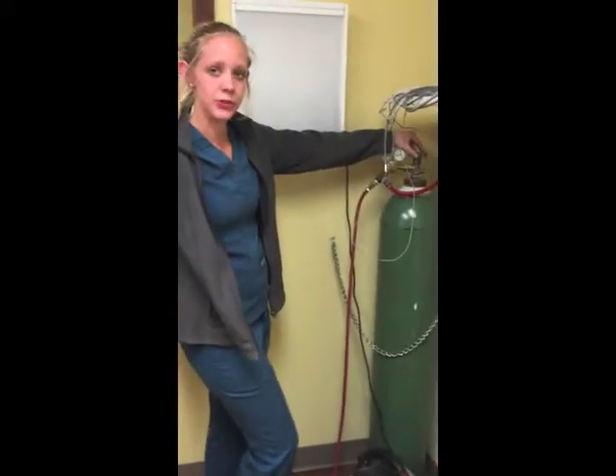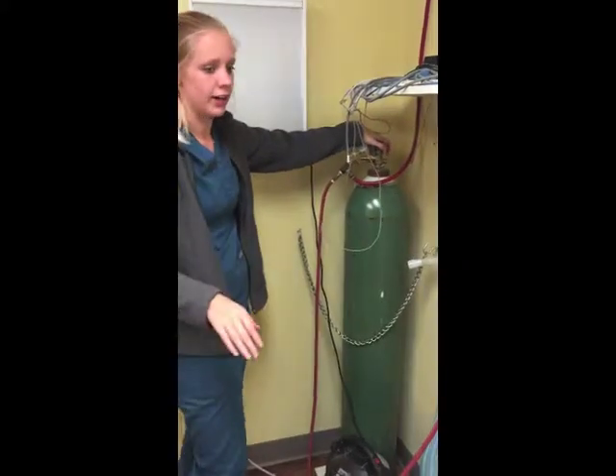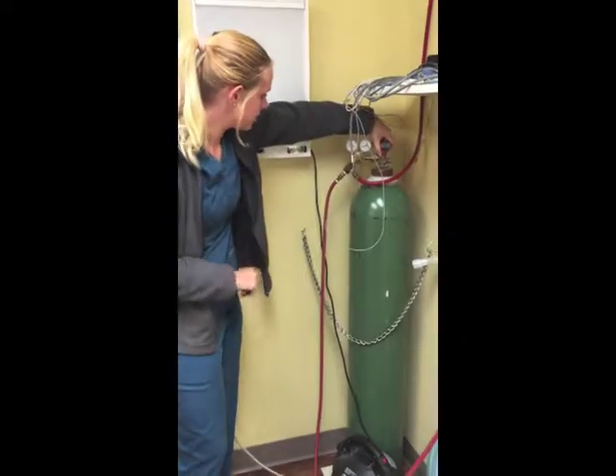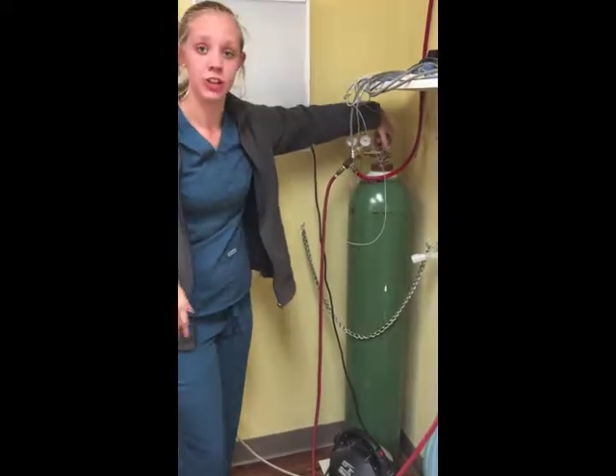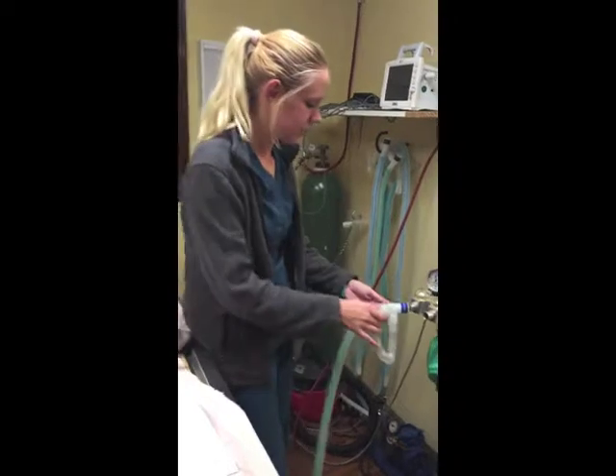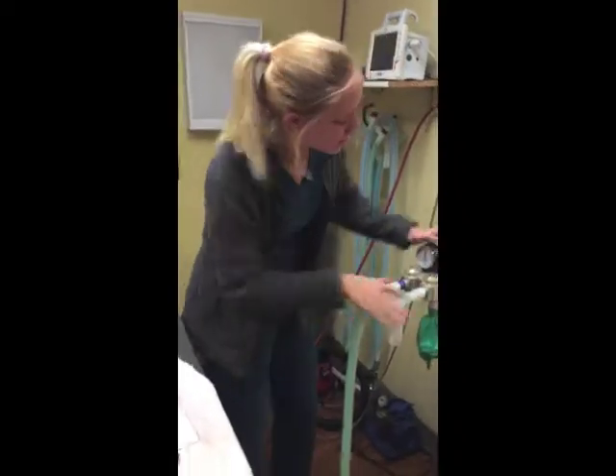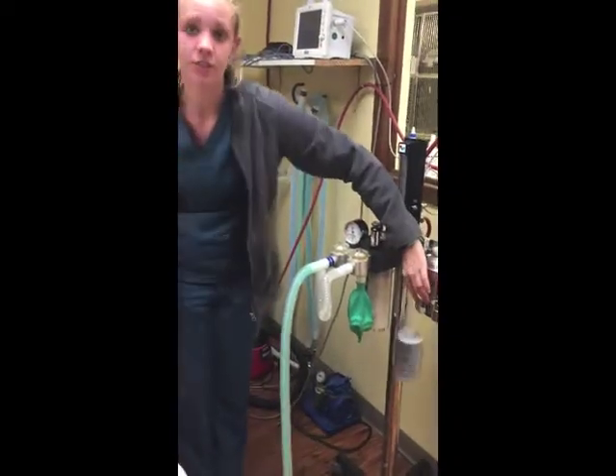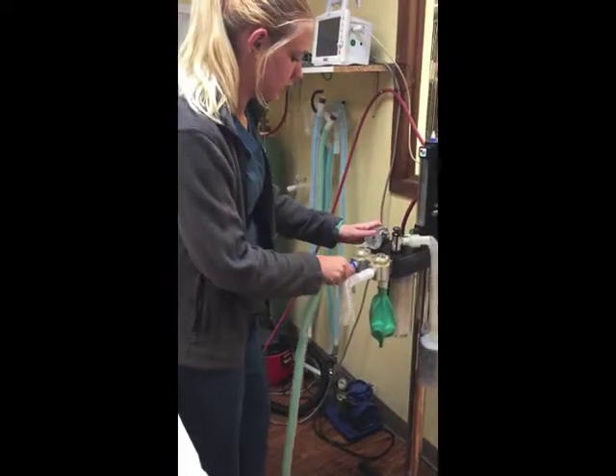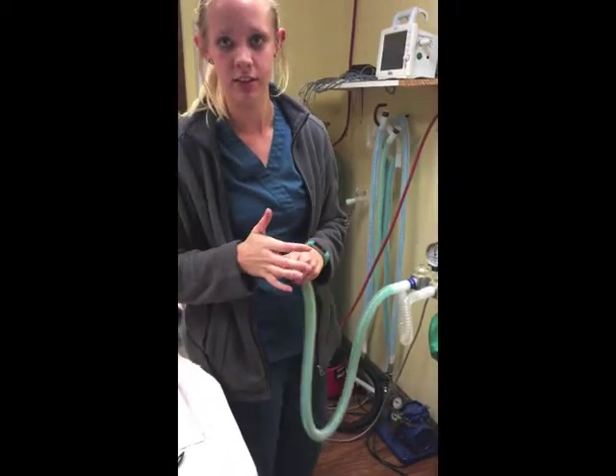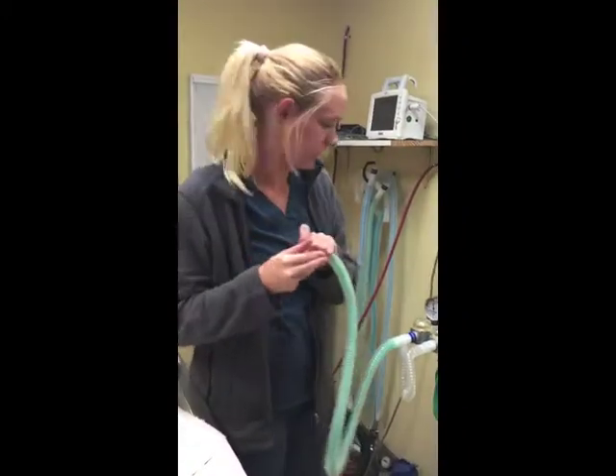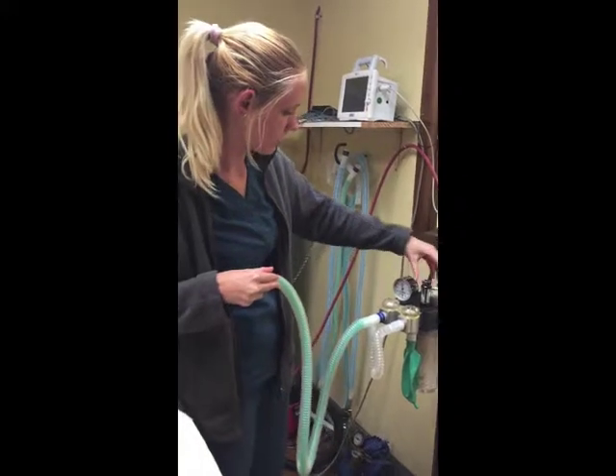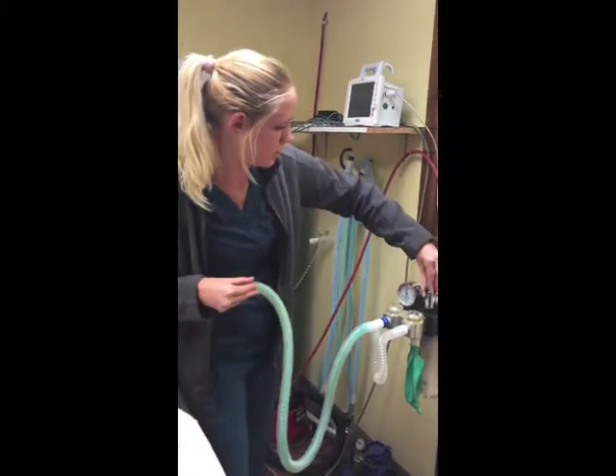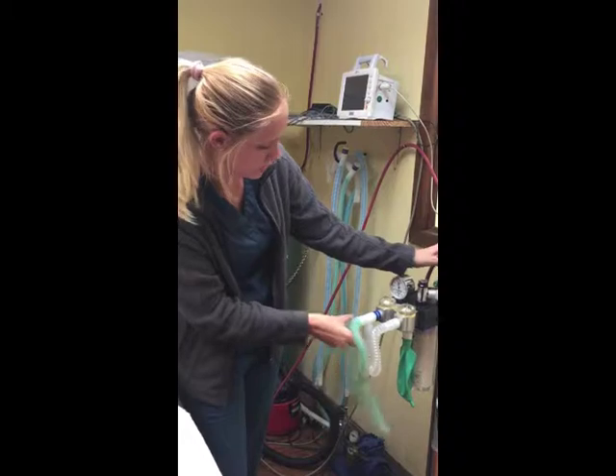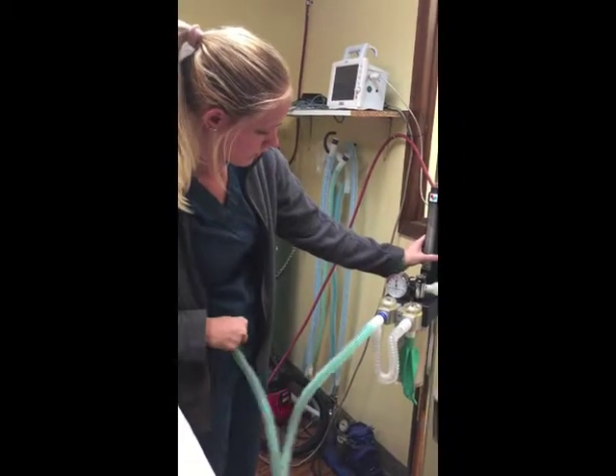On the first step of doing a leak test, you want to make sure that your anesthesia machine is hooked up to your oxygen and that your oxygen is turned on. And so you want to attach the circuit that's going to be used. Check your vaporizer that there's enough anesthesia in it for it to be used, and then on this end you'll put it against your hand. So you have the end against your hand, and then you close the pop-off valve, and then you hit the flush valve, and you have the pressure read to 40.